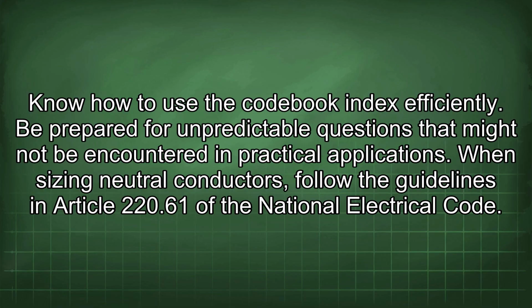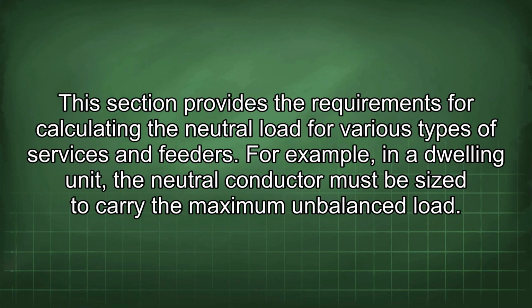When sizing neutral conductors, follow the guidelines in Article 220.61 of the National Electrical Code. This section provides the requirements for calculating the neutral load for various types of services and feeders. For example, in a dwelling unit, the neutral conductor must be sized to carry the maximum unbalanced load.